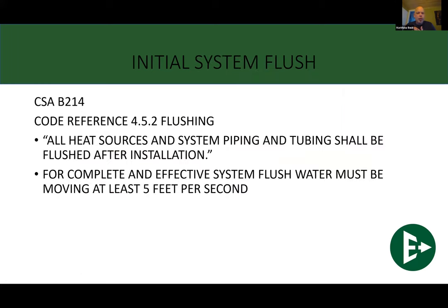Code reference, CSA B214 4.5.2: all heat sources and pipings and tubing shall be flushed after installation. So before you turn it on, all systems are designed to be flushed. Now let's talk about flushing real quickly. When we say flushing, we mean flushing. You've got to move that water through this system. What I recommend doing is isolating the boiler, having it on its own, and you can flush that individually. You want to be cognizant that you don't drive anything through that. But the rest of the system, you need to move water and you need to move it fast.